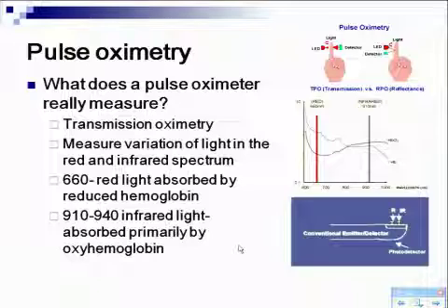So for a pulse oximeter to work, it has to know when the arterial pulse is coming in, because that way it only measures the saturation during that cycle, at the peak of the pulse. It doesn't want to look at the venous side, which is the downside. So pulse oximetry measures pulse, and then it measures oximetry, which is the oxygen level in your blood.